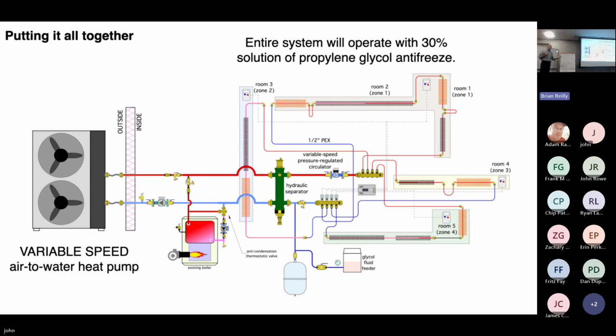If I can't access any of the piping, maybe I've got to do a better job on the thermal envelope, because I'm not going to be able to add heat emitters to the system. If I can access the piping, the next question is, where can I put those extra heat emitters? I can't put a 10-foot piece of baseboard in a wall that's only 4 feet long. Think about kitchens and bathrooms in particular. We often don't have wall space for that. So if I can't use baseboard, what else could I use?